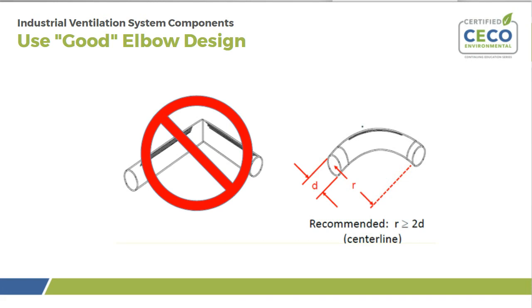Elbow design. The one on the left, obviously you don't want to do that. That's a 2-piece elbow. If it's handling an abrasive dust, it's going to blow a hole through the end of that elbow in a short matter of time. You want to go with that recommended elbow that has a centerline radius of 2 times the duct diameter or higher. The longer the sweep on that elbow, the greater the radius, the less friction loss you're going to have in that elbow.